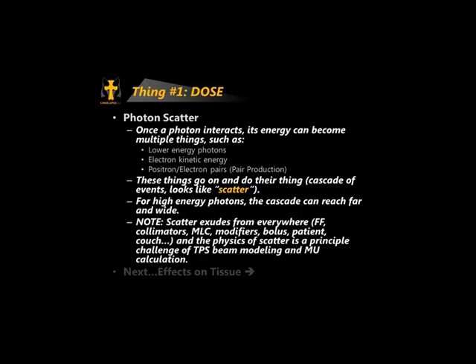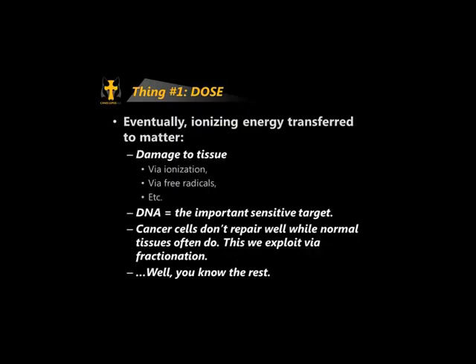Scatter presents the principal challenge of TPS beam modeling. When your physicist is working hard to model beams, a lot of what they're doing is modeling the effects of scatter on dose deposition — and directly related to that, monitor unit calculation. The more or less scatter there is clearly affects monitor unit calculations. Eventually there's ionizing energy transferred to matter, which can cause damage to tissue via ionization, or create a free radical — usually oxygen — that wants to cause damage.